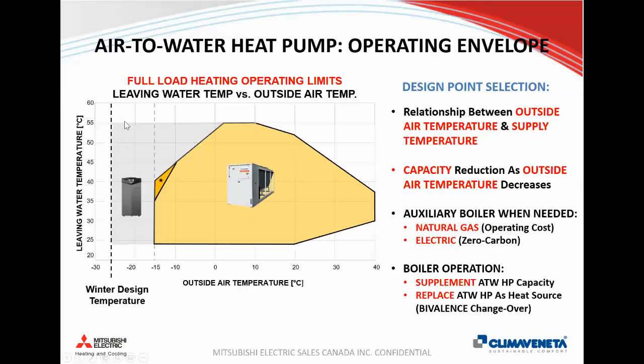The boiler can still provide 55 degrees if it wants to. So you need to take that into account. But it's basically about the return temperature to the heat pump. Depending on the return temperature from the system, if that's above the maximum leaving water temperature from the unit, then the heat pump can't add any heat to it.